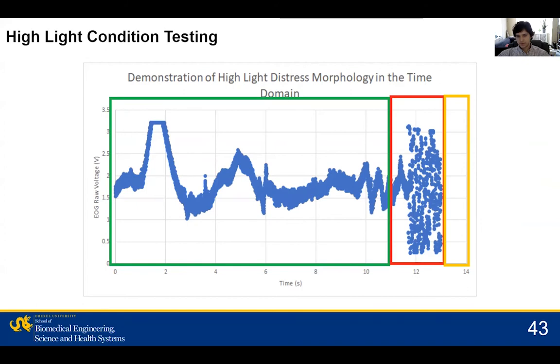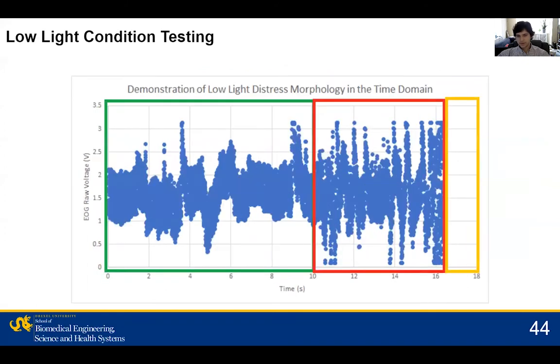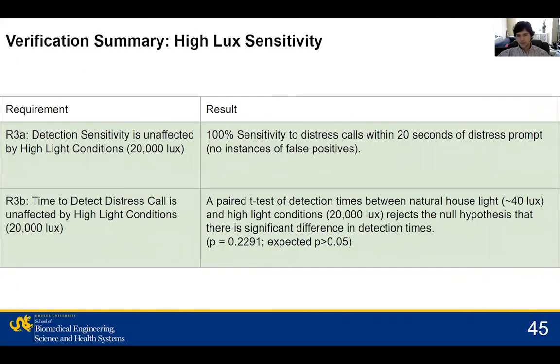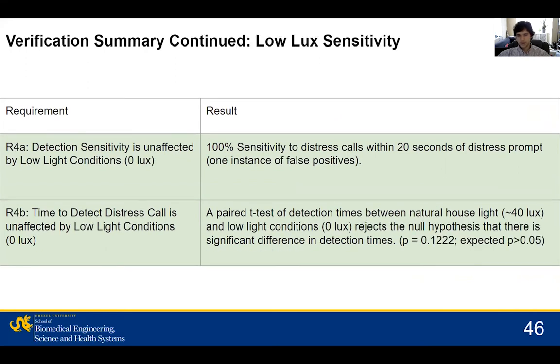But moving on to the graph at low light, you can see a serious drop in resolution. Fortunately, our device was still able to perform properly and within the 20-second time frame. But as you can see, there was a much longer detection period, which could bring more problems to light in larger sample sets. To summarize our testing results, the high-intensity light sensitivity testing did not result in any significant decrease in sensitivity or response time, and neither did the low light intensity portion of the test, although there was an increase in response time.